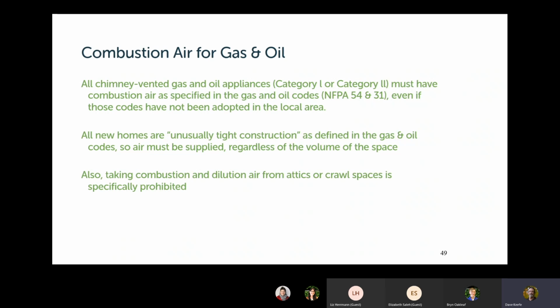Also, taking combustion and dilution air from attics and crawl spaces is specifically prohibited according to the Vermont Energy Code, even though those things are allowed in the national gas and oil codes. So you have to provide combustion air all the time, regardless of the volume of the space, and you have to provide it all the way from outdoors, not from a crawl space or an attic.